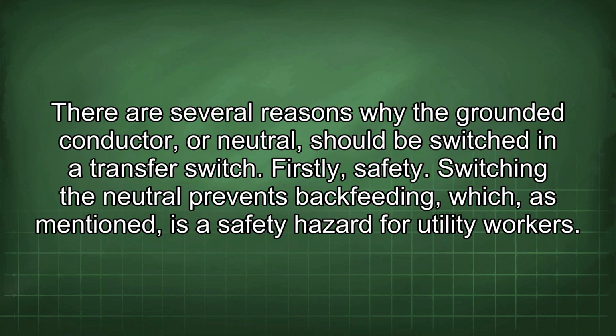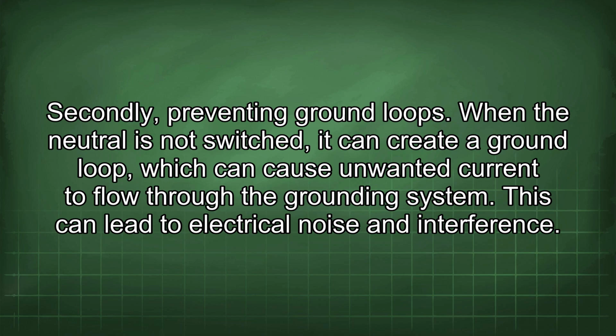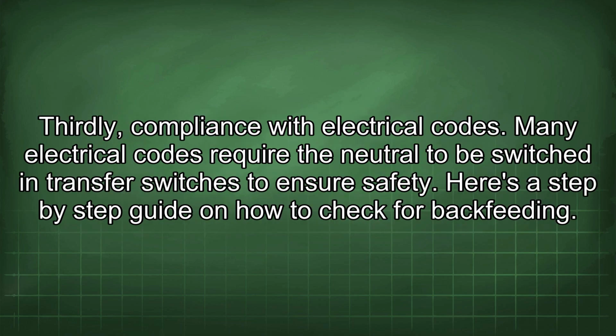There are several reasons why the grounded conductor, or neutral, should be switched in a transfer switch. Firstly, safety. Switching the neutral prevents backfeeding, which, as mentioned, is a safety hazard for utility workers. Secondly, preventing ground loops. When the neutral is not switched, it can create a ground loop, which can cause unwanted current to flow through the grounding system. This can lead to electrical noise and interference. Thirdly, compliance with electrical codes. Many electrical codes require the neutral to be switched in transfer switches to ensure safety.